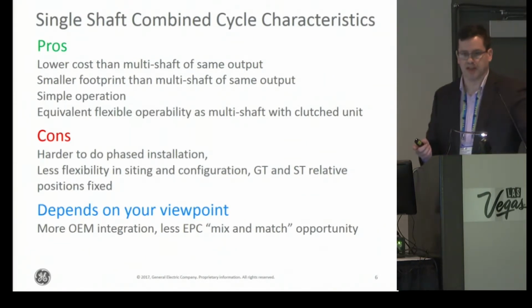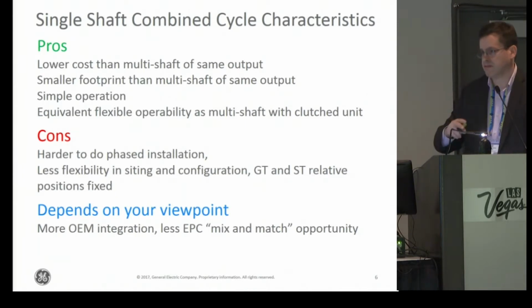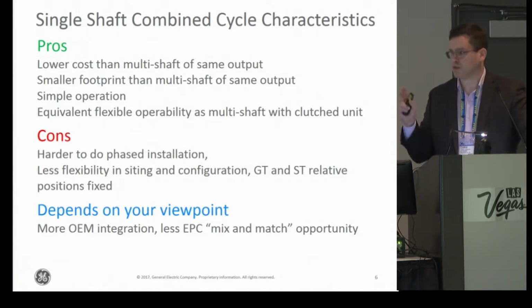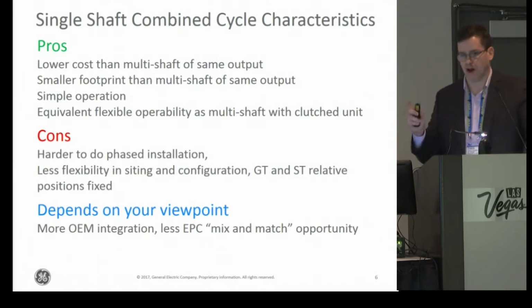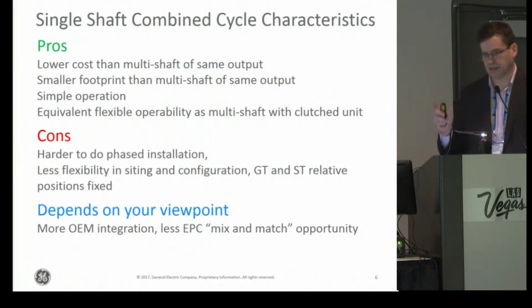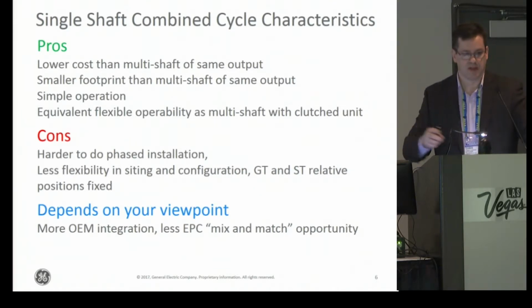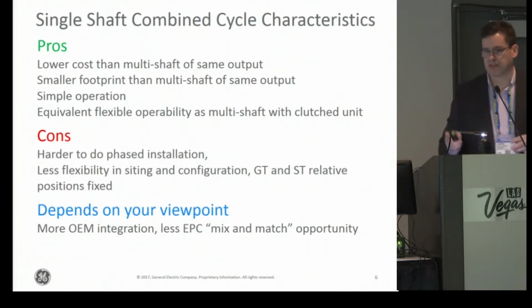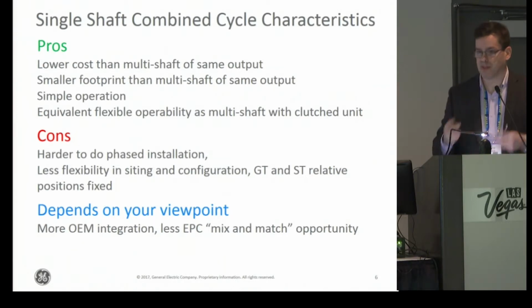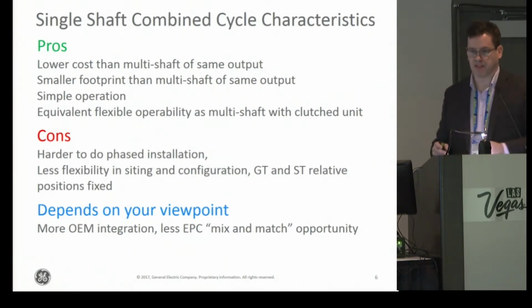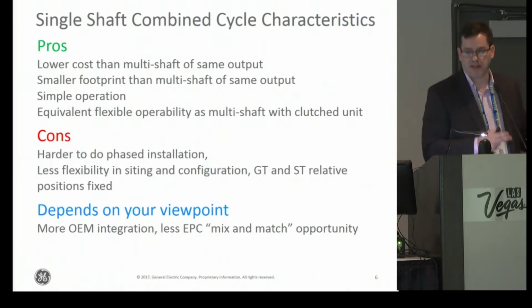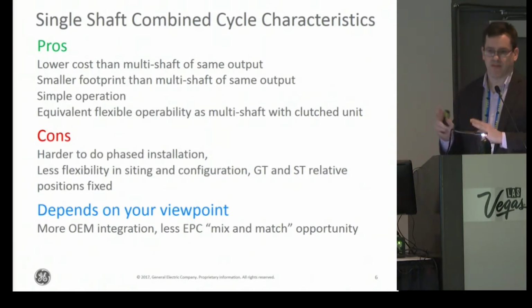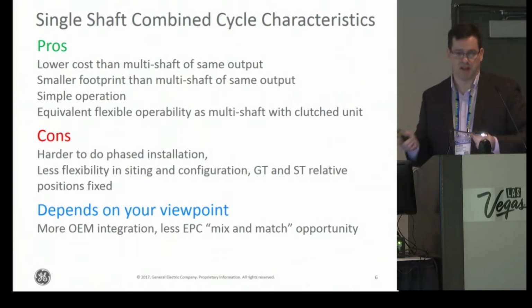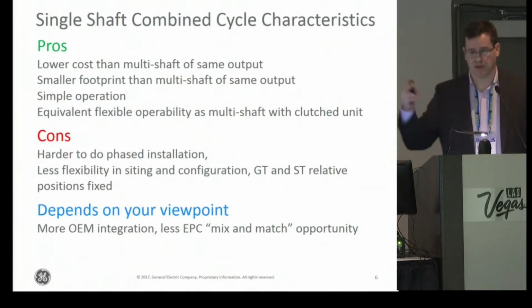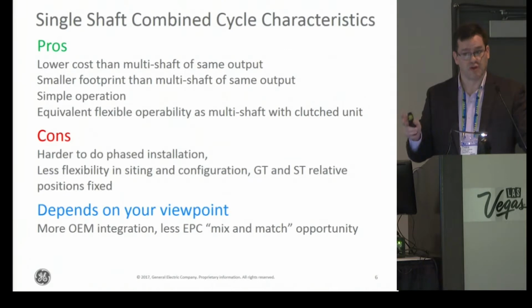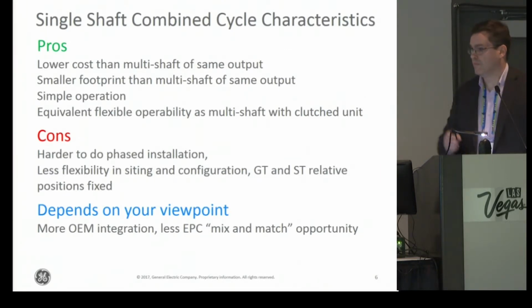Now, that does have some cons, some of which aren't as applicable in, say, North America. One of the cons on a single shaft is it's a little harder to do a phased installation where you want to run the gas turbine first and have it online while you're still building the steam turbine. We see this more in, say, Latin America or other places where they need power quickly. They may want to do a phased installation, get the gas turbine online as soon as possible, and then keep building the steam turbine. For that, multi-shaft is a little better. It's a lot easier to execute than trying to build a single shaft with the gas turbine first. You can do it, but it has lots of complications.